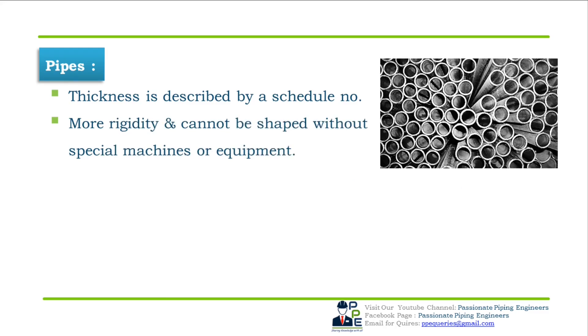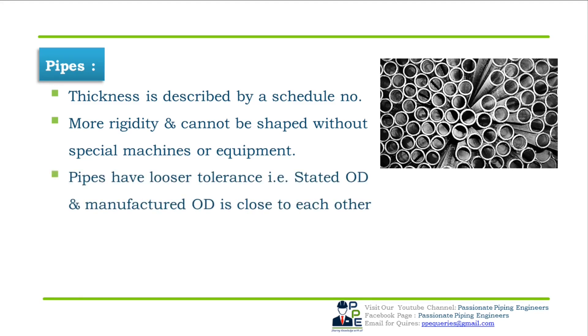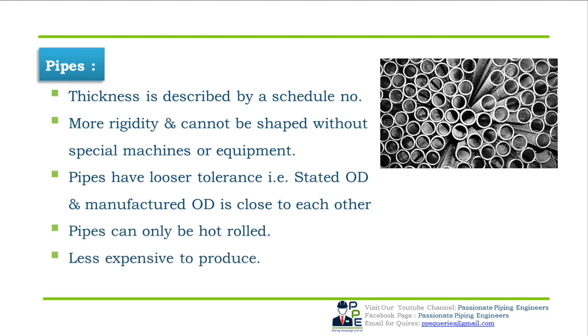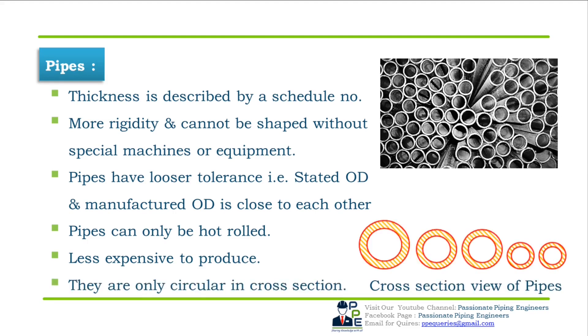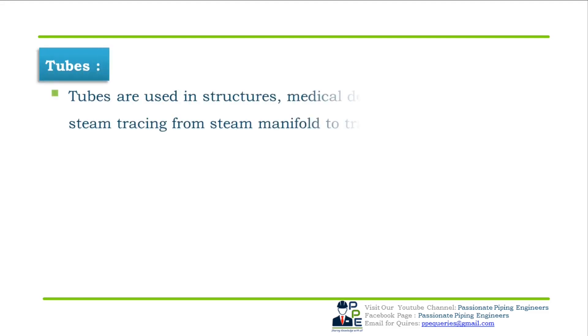Pipes are more rigid and cannot be shaped without special machines or equipment. Pipes have looser tolerances — that is, the stated OD and manufactured OD are usually close but approximate to each other. Pipes can only be hot rolled; they are less expensive to produce. They are only circular in cross-section.